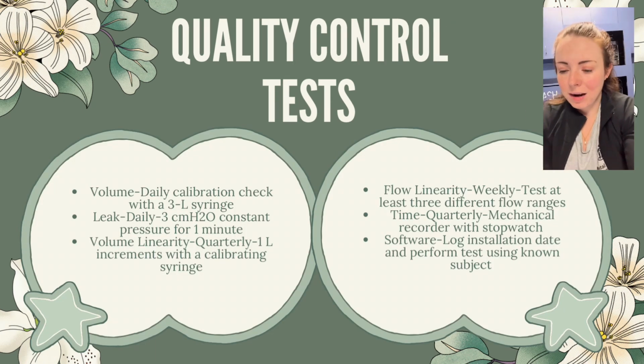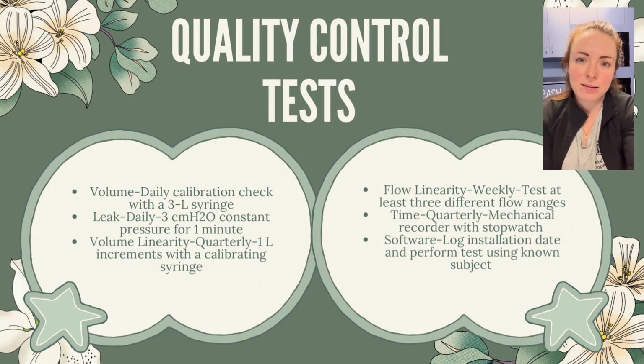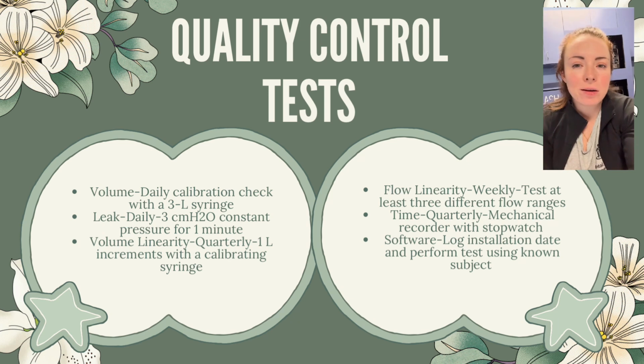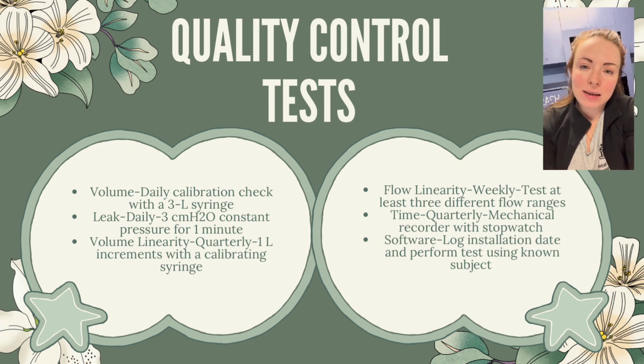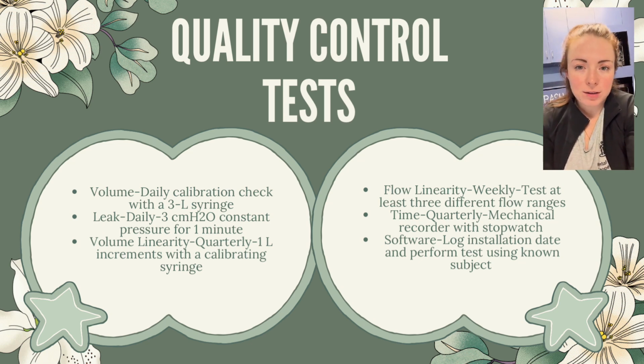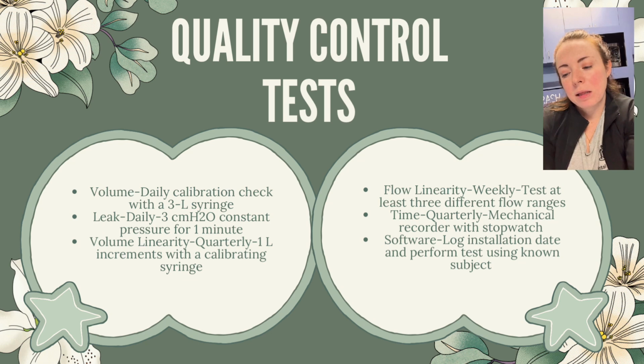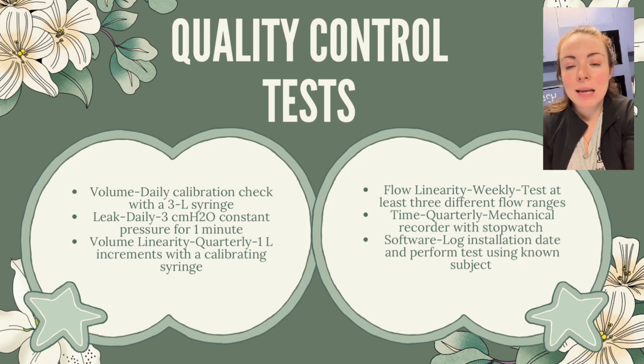Okay, so this next slide is just kind of looking at what are some of the quality control tests that are done on a regular basis. Well, it talks about volume, that is a daily test, where a calibration check is done with a 3-liter syringe. We talk about a leak, that is also a daily test. So we have to see about 3 centimeters of water, constant pressure for 1 minute, to determine if there's a leak. And then we have volume linearity, which is a quarterly check, and that is 1 liter increments with a calibrating syringe. A flow linearity, that's a weekly test, where we test at least 3 different flow ranges.